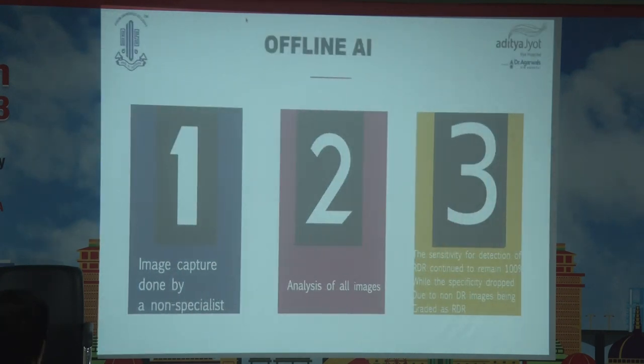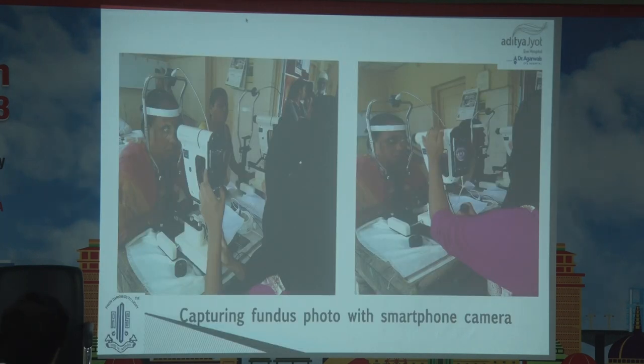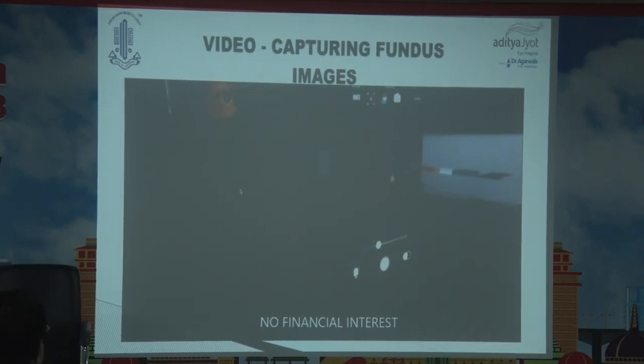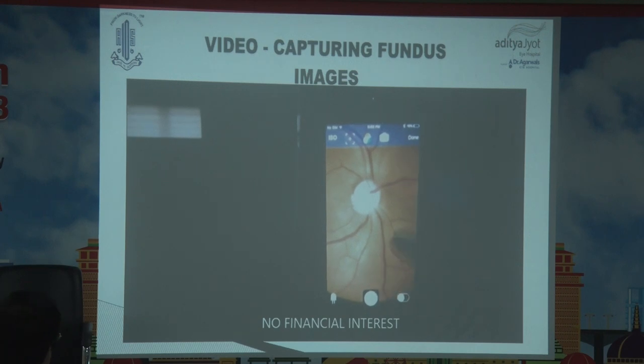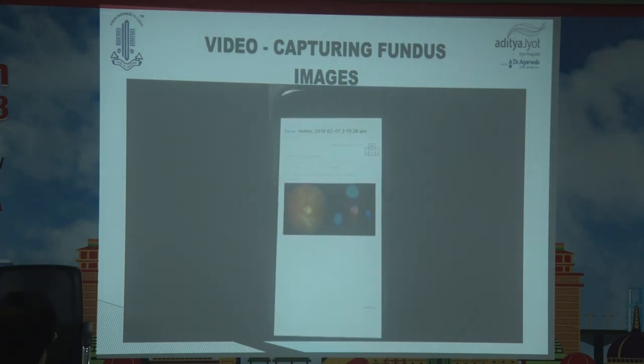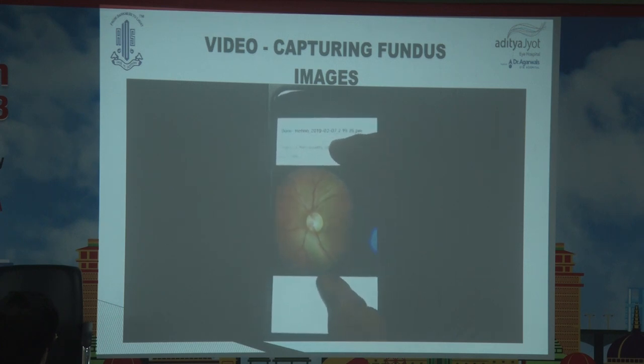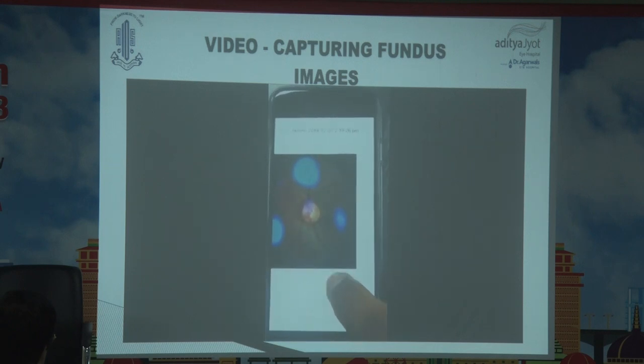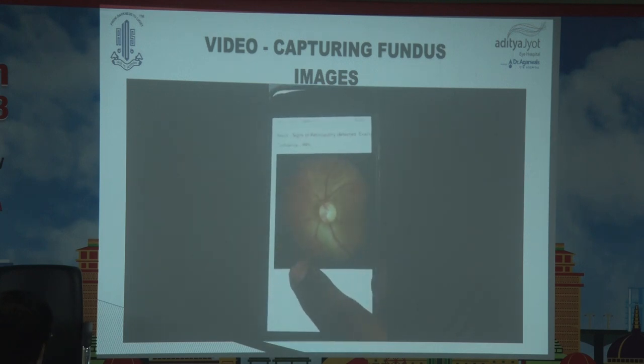Here offline: capture the image, analyze the image, and the sensitivity of detecting diabetic retinopathy. You can see the Remidio camera, where we have trained non-medical staff to handle it and take photographs. This video shows that you can focus and take a beautiful photograph of the retina. You can enlarge and save it. You can check the quality score — it shows 99% confidence. This is applied to the AI software; the blue markings identify the abnormal color differences in the retina, comparing to thousands of images stored on the mobile phone. Without internet, within 28 seconds, it gives an answer on whether to refer.